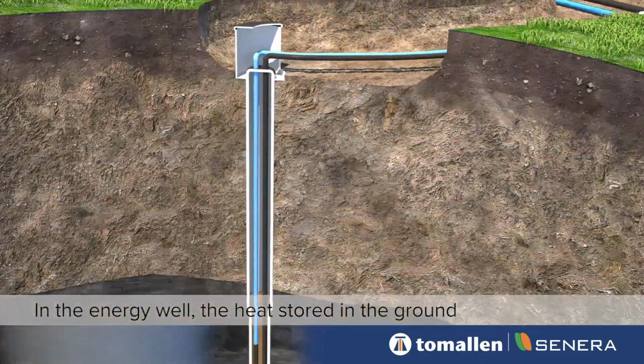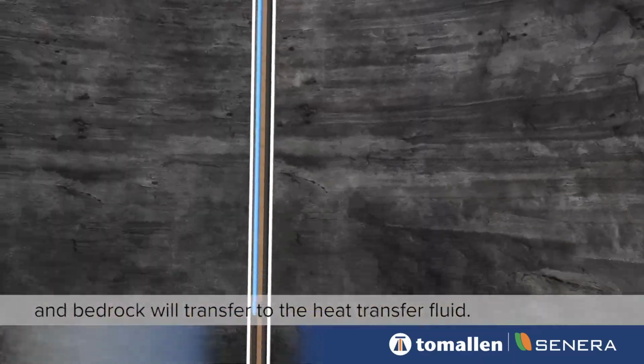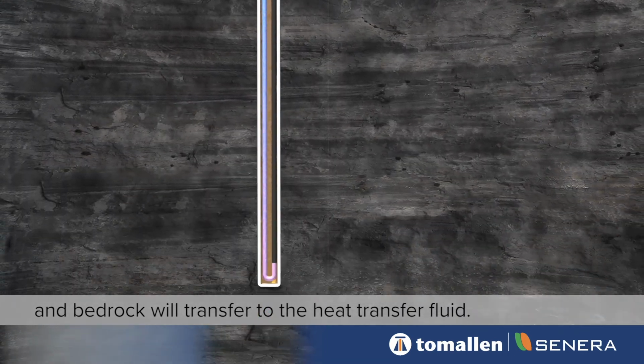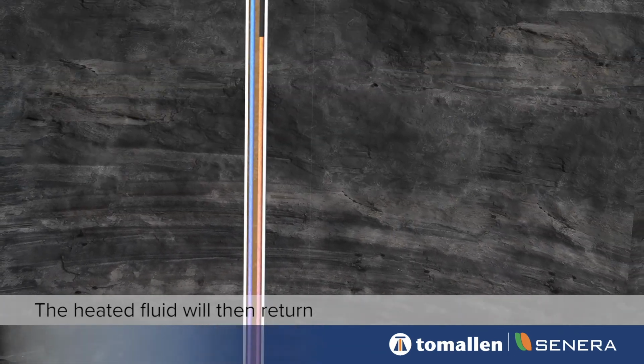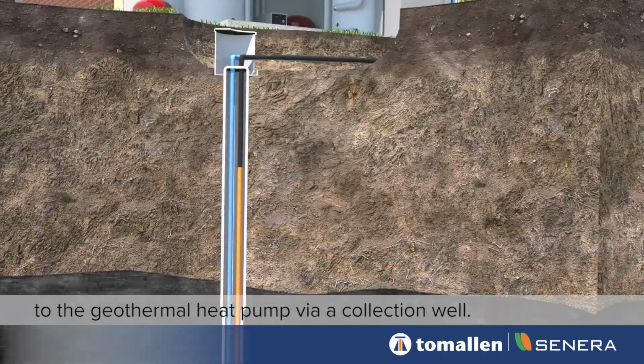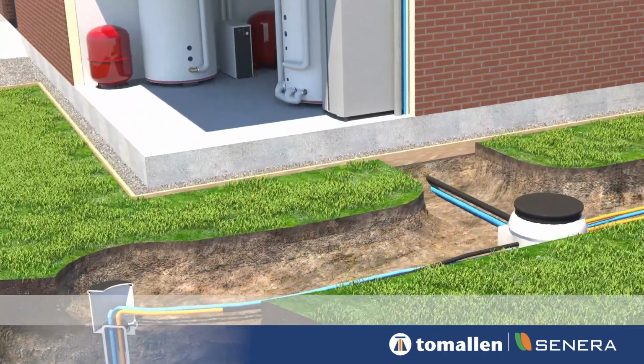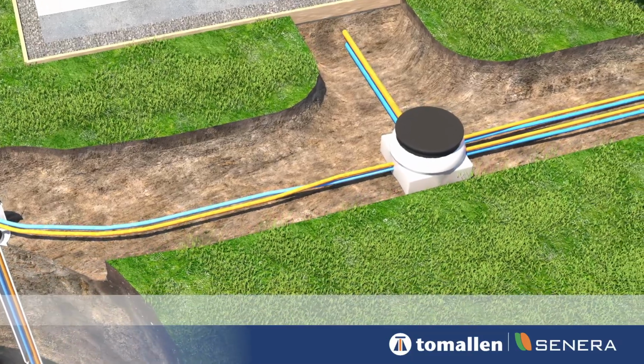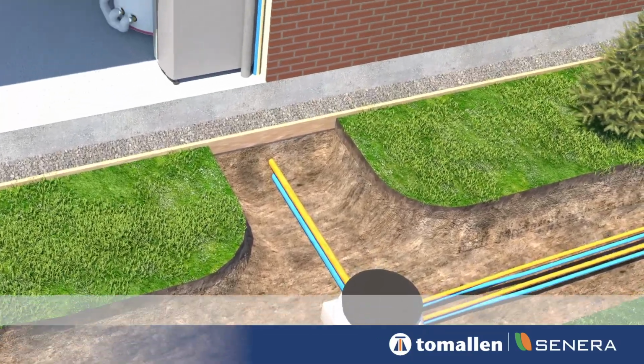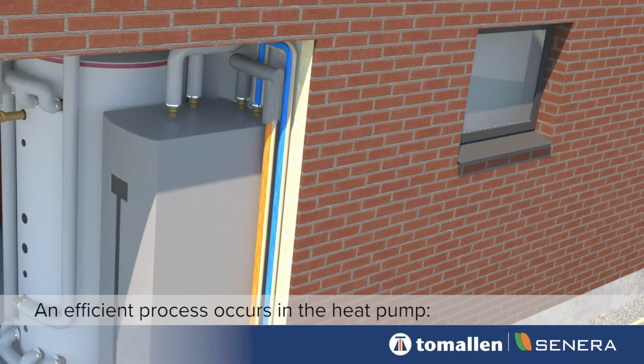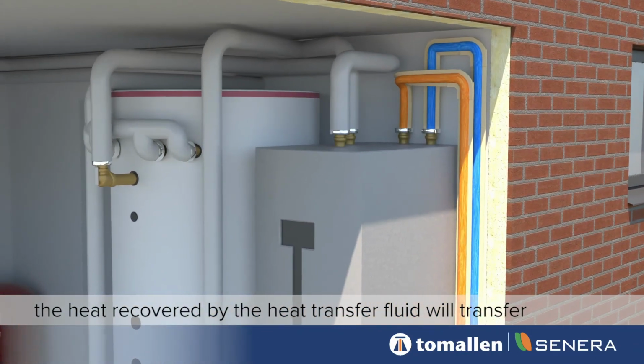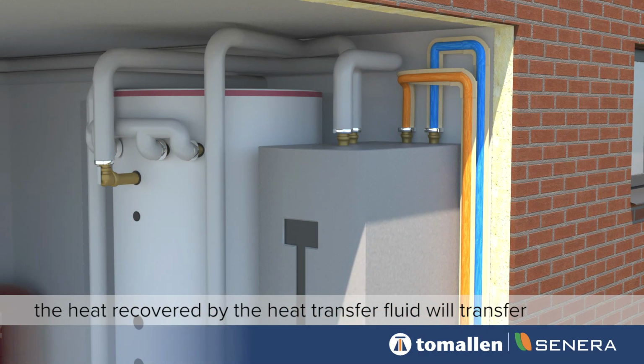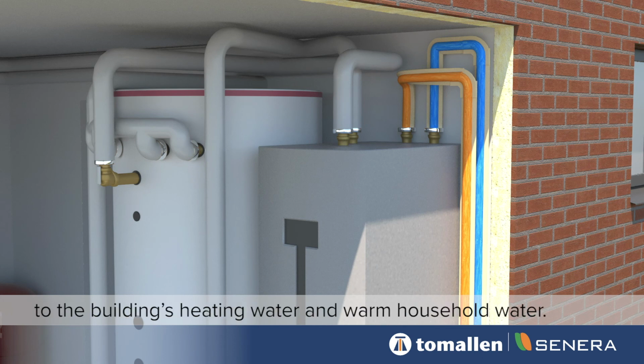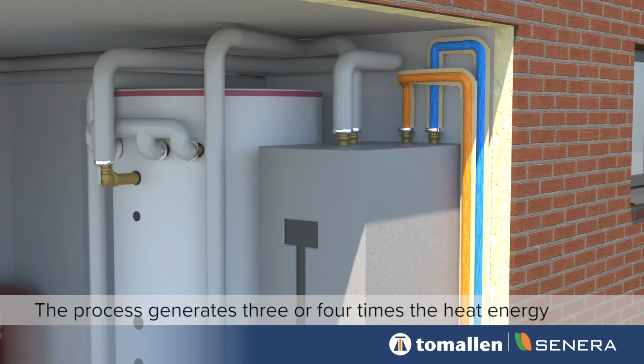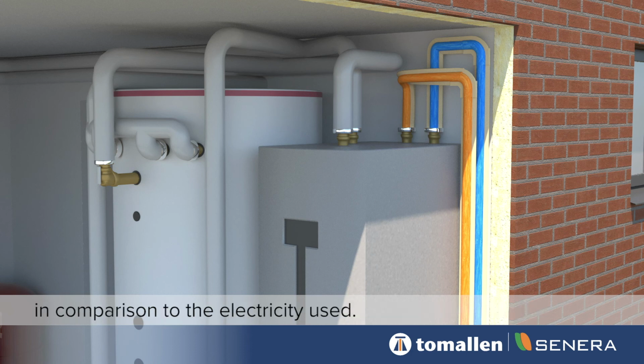In the energy well, the heat stored in the ground and bedrock will transfer to the heat transfer fluid. The heated fluid will then return to the geothermal heat pump via a collection well. An efficient process occurs in the heat pump. The heat recovered by the heat transfer fluid will transfer to the building's heating water and warm household water. The process generates 3 or 4 times the heat energy in comparison to the electricity used.